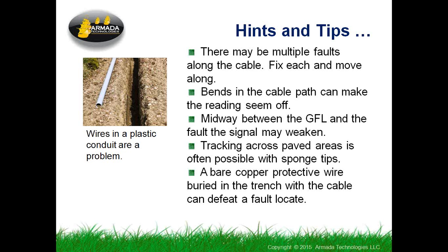There are some good tricks about testing on paved areas. They involve putting wet sponges on the tips of the probe. There's quite a bit of moisture in things like concrete, for example. If you put wet sponges on the tips, you can actually continue to do your fault locating under concrete. Some of that's true of pavement as well, but you can also do a trick with extending the A-frame across the road with a wire and a second probe like a screwdriver. That's a different technique that I won't go into great detail on here.